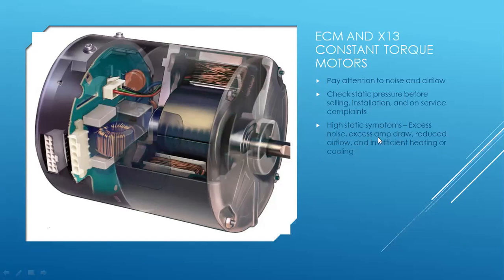Also excessive amp draw. When I was first taught to sell ECM motors, ECM motors solved every problem in the world, and they cost as much as a light bulb to operate. And in a lot of cases, that's true. But if you're in a high static situation, you're taking what you consider to be an energy efficient motor and you're pushing it past its boundaries. So it's having to work 120%, 130% to move the air it thinks it has to move. By doing that, you get extreme excessive noise and excessive amp draw. So whatever it should be, it's going to be double or triple in some cases.